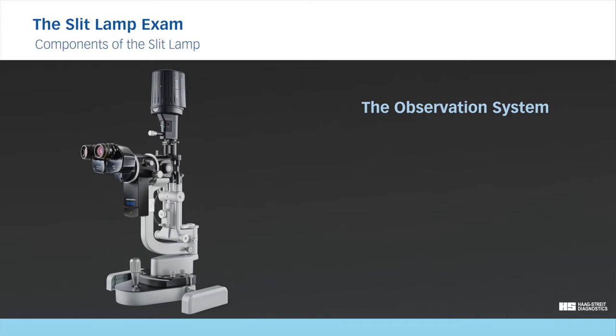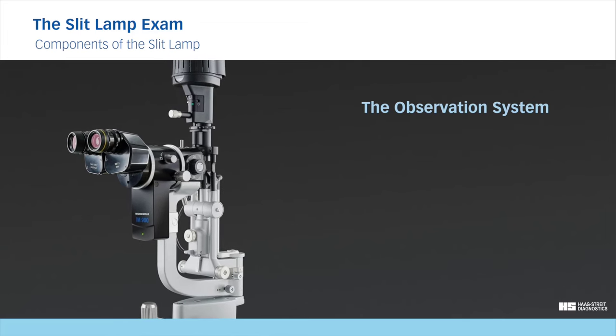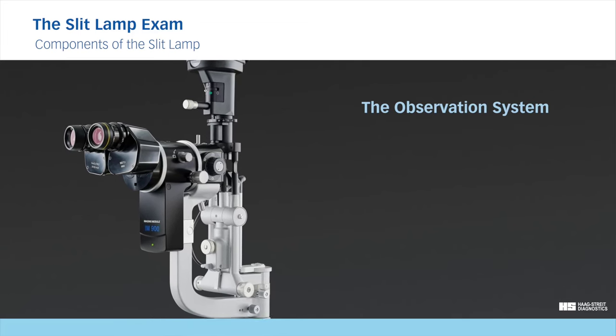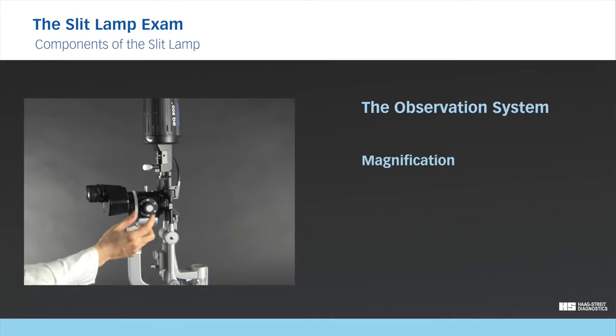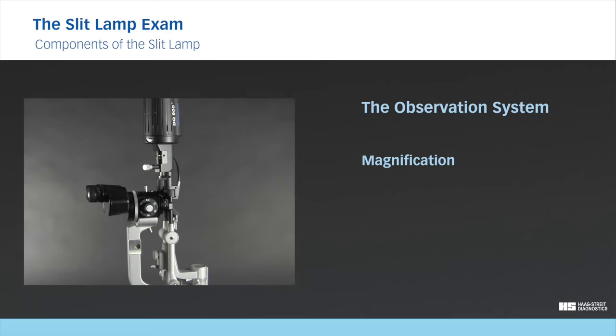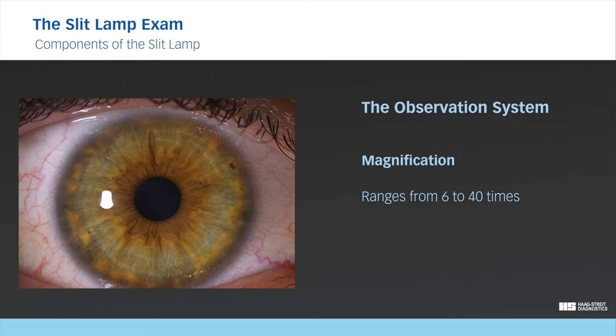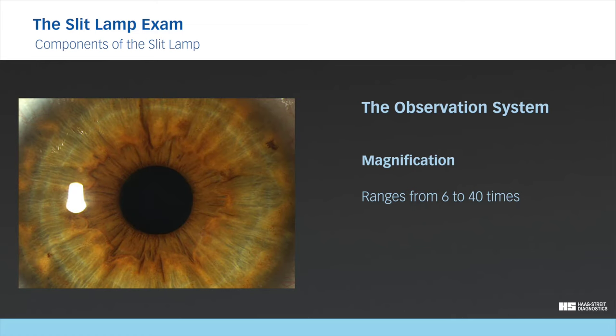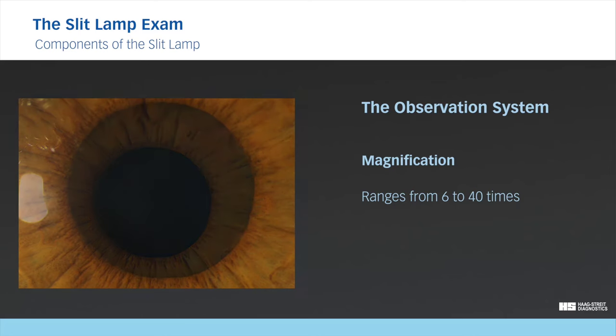The observation system provides a magnified view of the structures being observed. The magnification can easily be changed by turning the magnification dial to the desired level. In most slit lamps, the magnification ranges from 6 to 40 times. This allows the observer to use the appropriate magnification to obtain an overall view of the eye or to zoom in to observe subtle changes in greater detail.